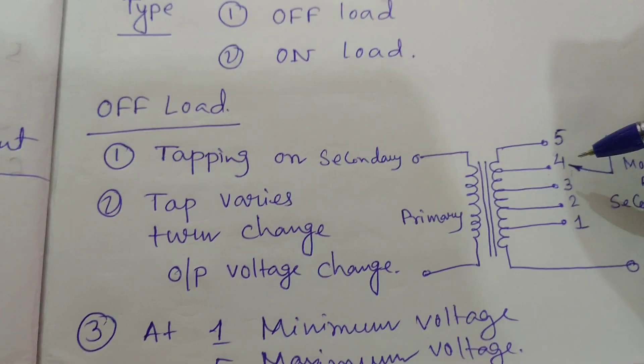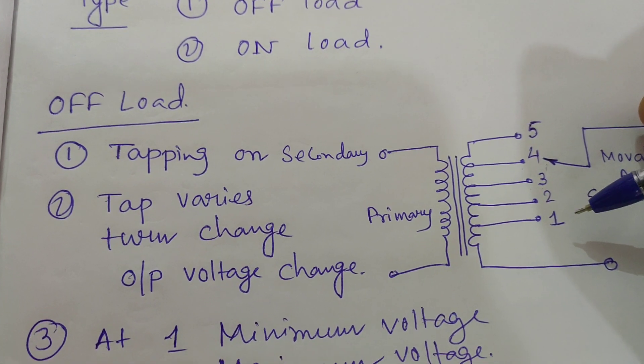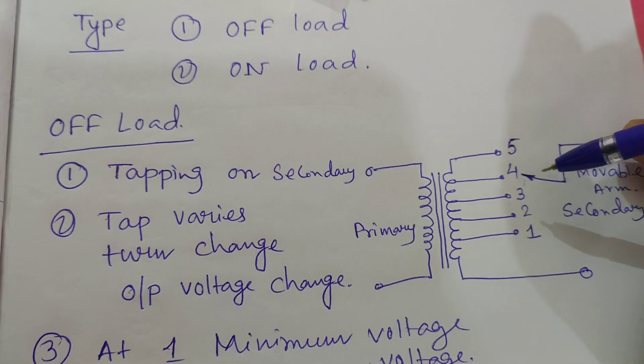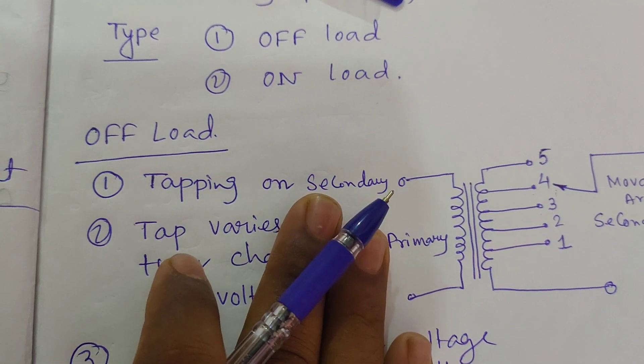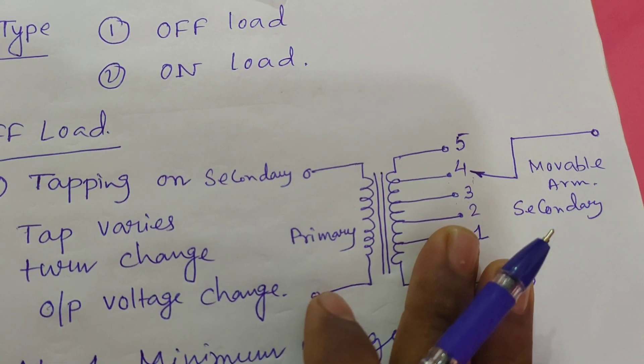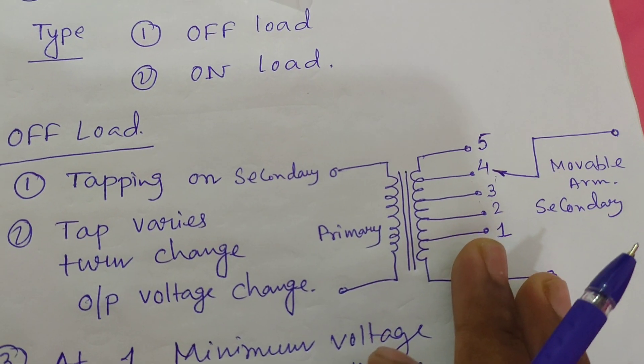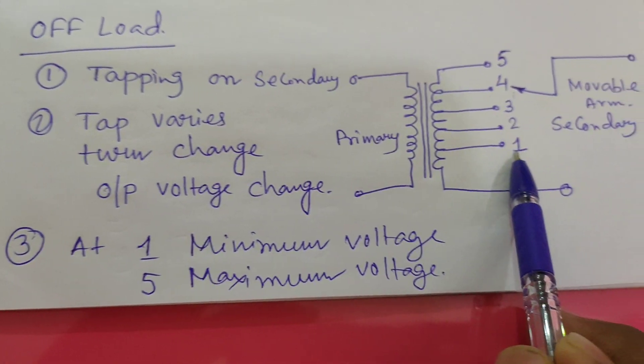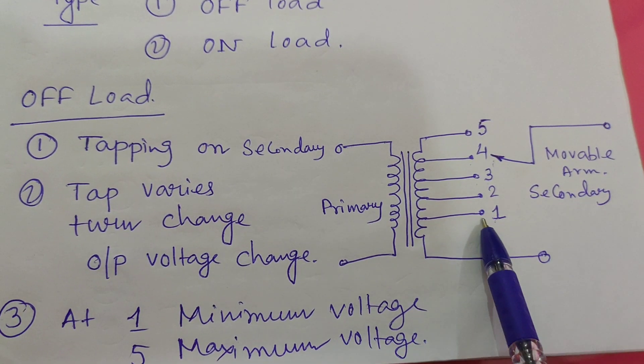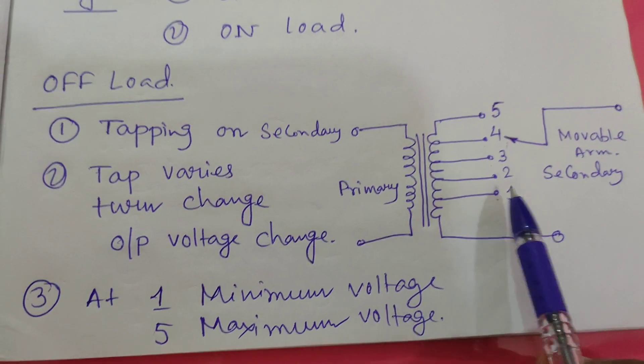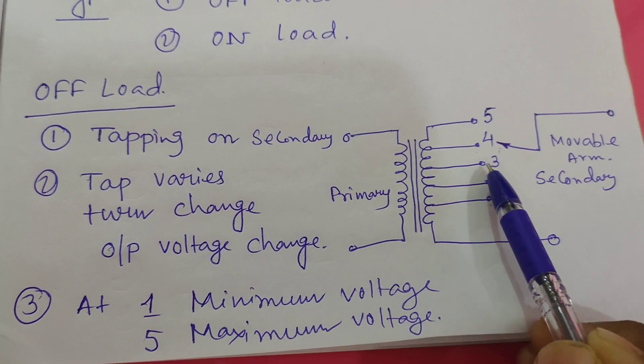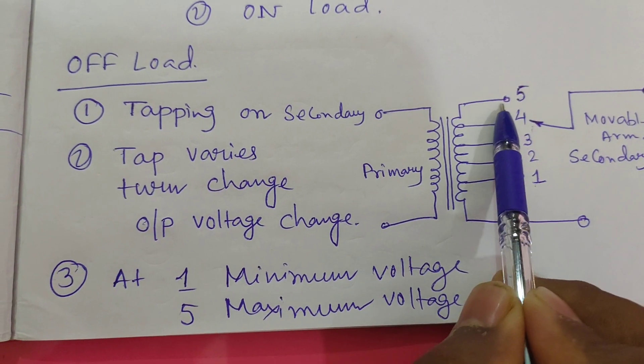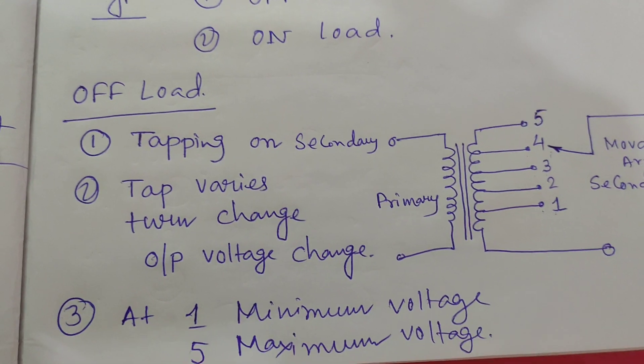If the number of turns is decreasing, you will get the voltage decreasing. If you increase the tap from 1 to 5, you are increasing the voltage because the primary side EMF or alternator voltage has decreased, and accordingly you are maintaining your voltage as per requirements. At terminal 1, the movable arm gives the minimum voltage. Moving up increases voltage, and at tap 5 the maximum voltage is obtained.